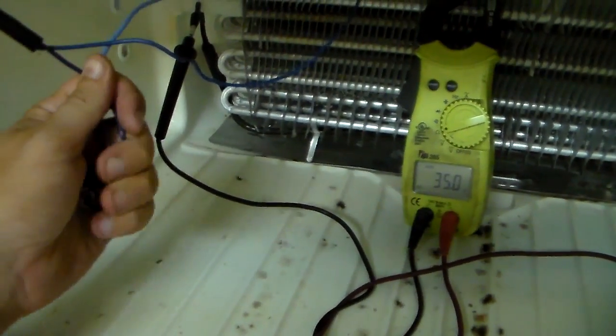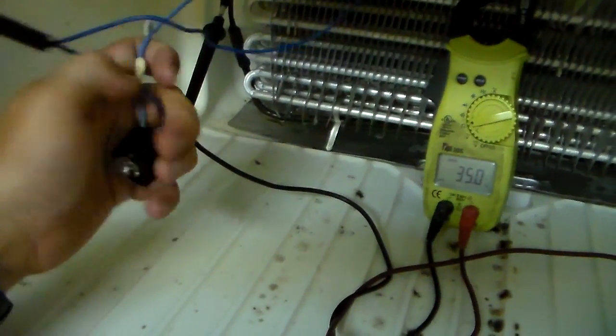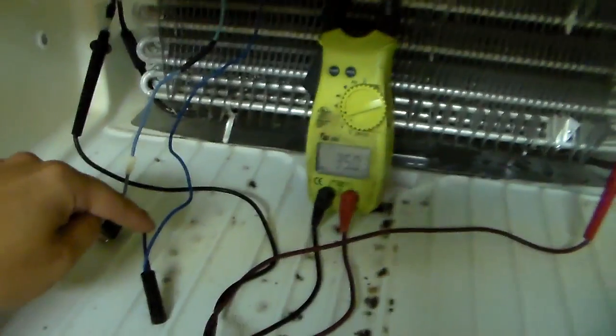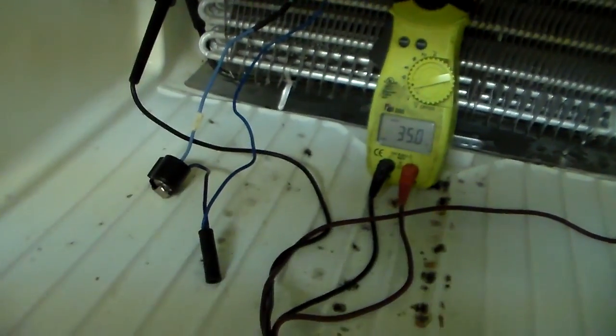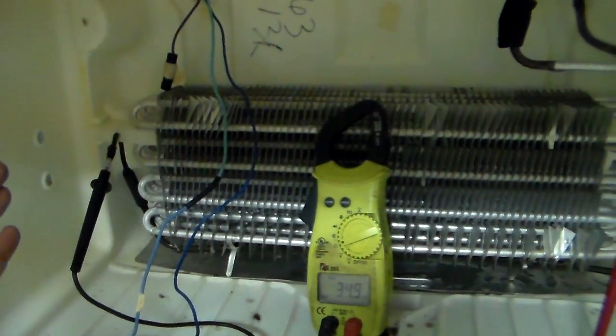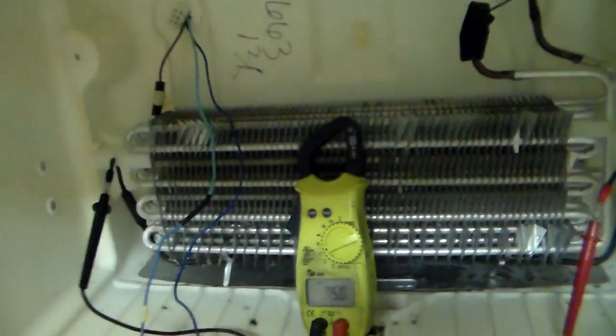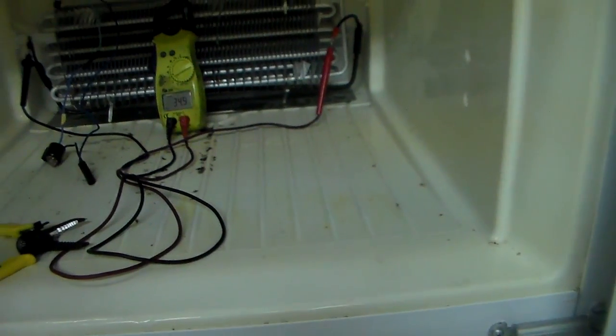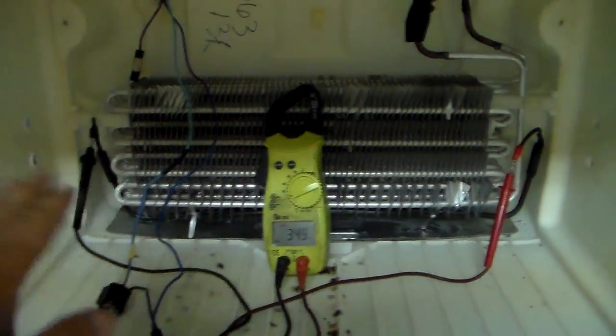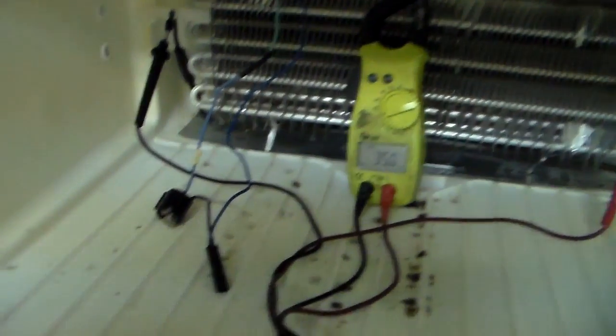Okay, after you've let the thermostat part sit in the glass of cold water for about five minutes, you want to test your two leads. You want to have a completed circuit through - in through one wire, out through the other. I mean, if you put this in defrost timer - if you put the defrost timer in defrost and you go ahead and... I'm not going to recommend it. I went as far as checking the machine with it plugged in as I would recommend for you guys to do. The simplest check was put it in defrost, if the heater comes on you know the timer's bad. But we put this in defrost, the heater did not come on. We check the heater with it unplugged, we know the heater's good. Now we're going to check this.